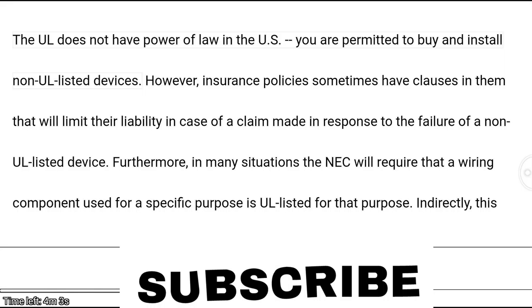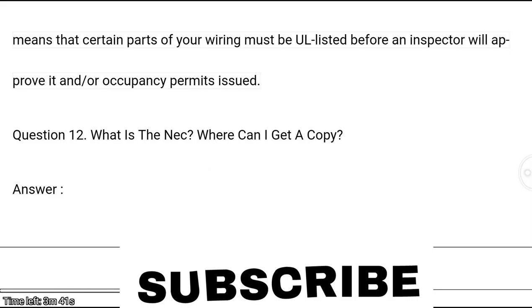UL does not have power of law in the U.S. — you are permitted to buy and install non-UL-listed devices. However, insurance policies sometimes have clauses that limit liability in case of a claim related to a non-UL-listed device. Furthermore, in many situations the NEC will require that a wiring component used for a specific purpose is UL listed for that purpose, meaning certain parts of your wiring must be UL listed before an inspector will approve it or issue occupancy permits.